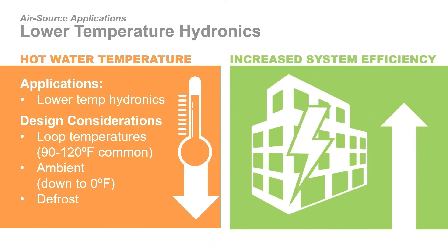Let's take a look at a new heating trend. Many new construction heating systems are going to lower temperature hot water requirements, ranging from around 90 to 120 degrees depending on system design and building location. Many existing heating systems were designed in the 160 to 180 degree range. Lower heating temperatures are significantly more efficient, allowing for higher system COPs. For heating systems with lower grade requirements, air source heat pumps can be a great design consideration for electrification. In these systems, an air source heat pump can be used as the sole heating source for the building, with a boiler backup as an option if needed. Many heat pumps available today can provide these lower heating temperatures at an ambient range down to zero degrees. With the many sizes available, there is quite a bit of flexibility when evaluating this potential system solution.